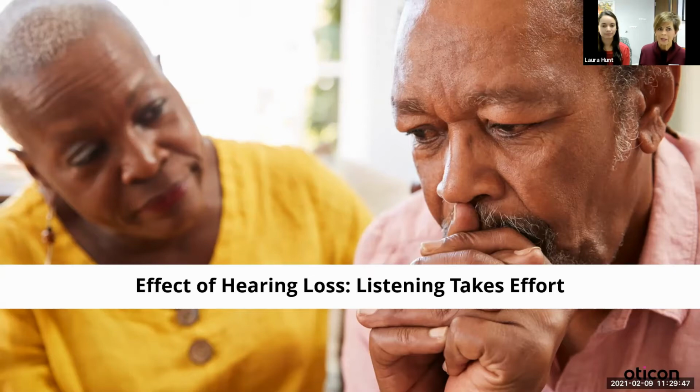The other thing that we're doing in order to help people, because the speech is being pulled down through the mask, is that we are offering a speech program or a masked program. We're actually boosting the speech frequencies in the hearing aid. So when you have the mask over your mouth, now you're muffled, but in that speech or mask program, you're getting more boost. I like to say to the patients that it's kind of like wearing sunglasses in the house, right? It's too dark when you have sunglasses in the house, but when you go outside, they work perfectly.